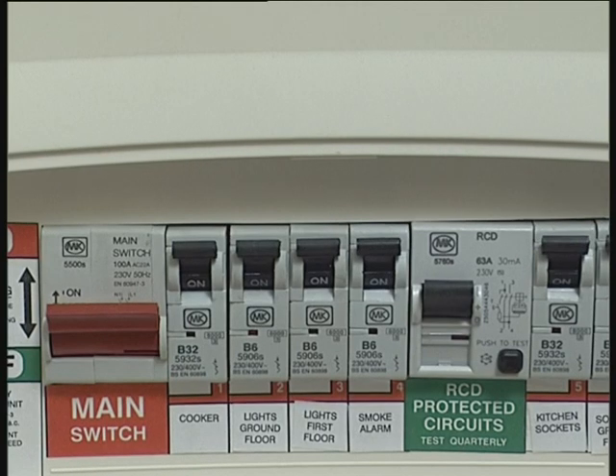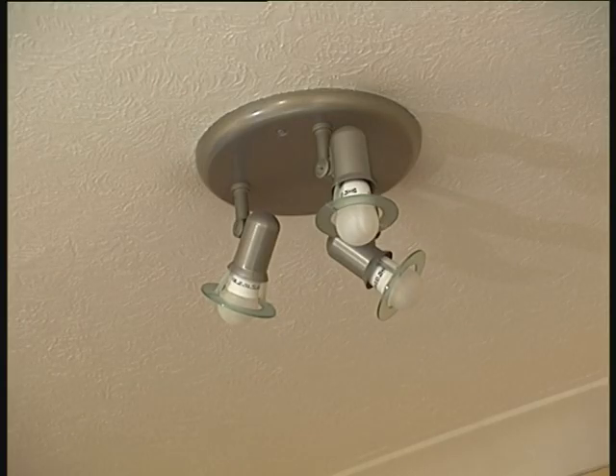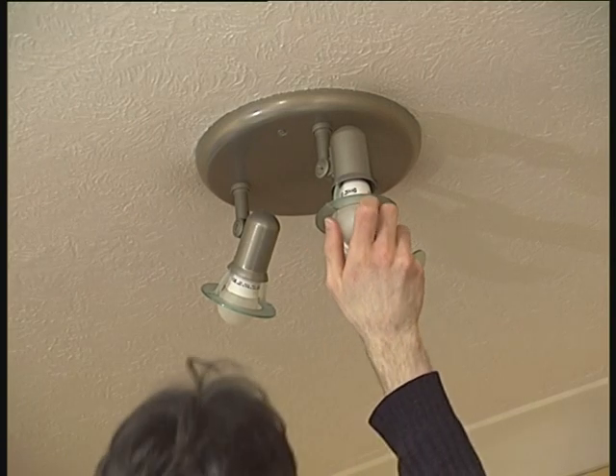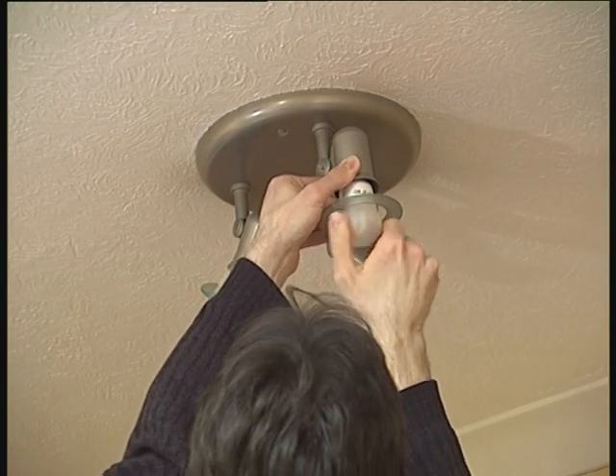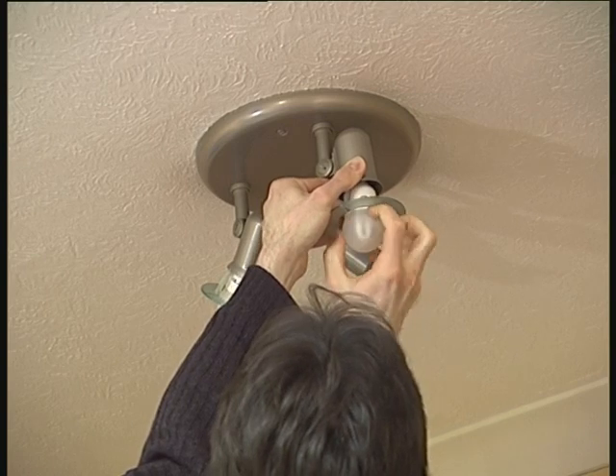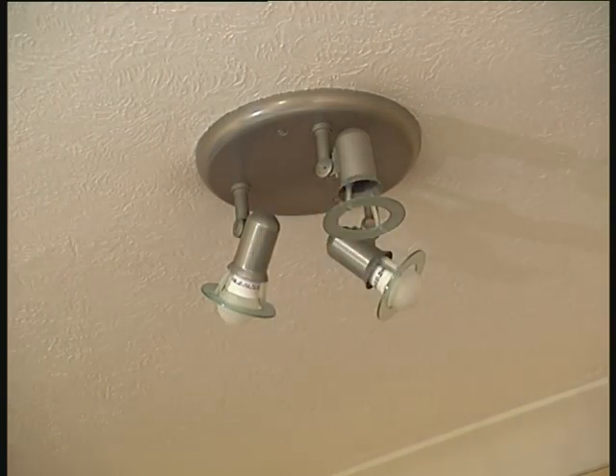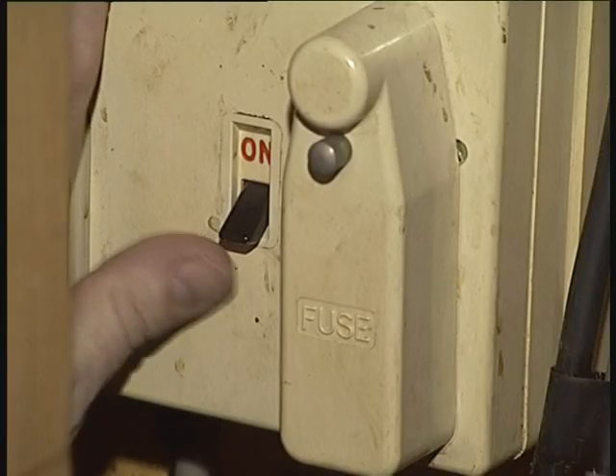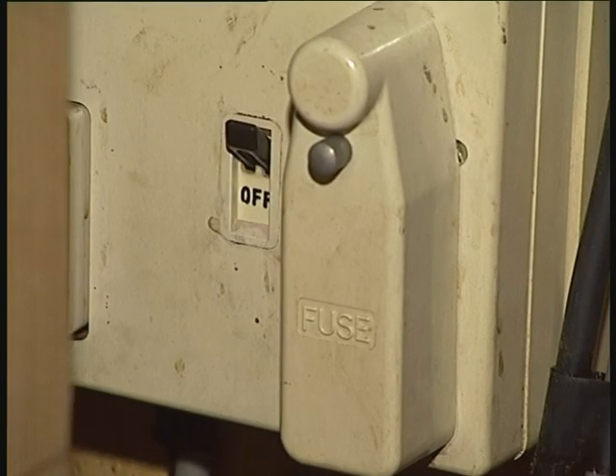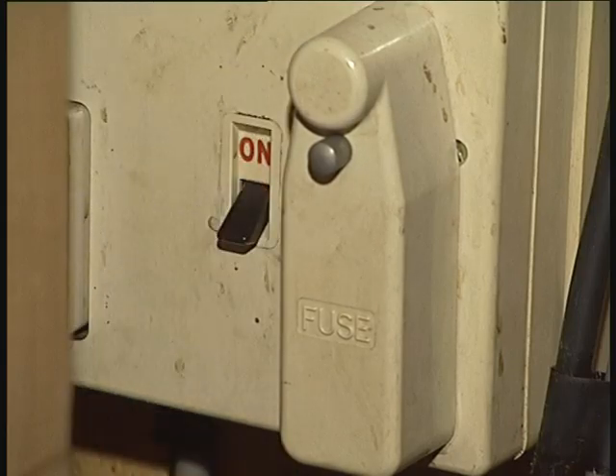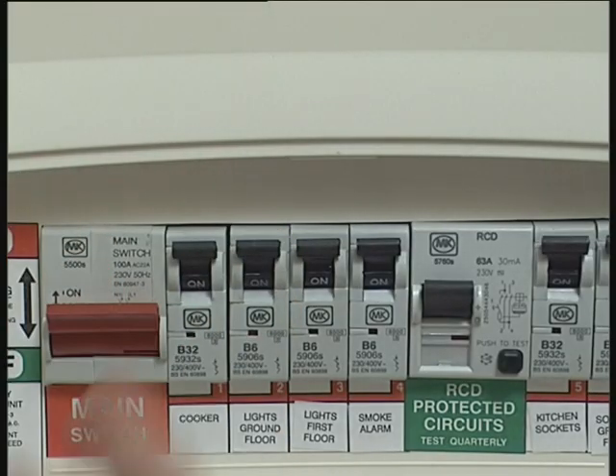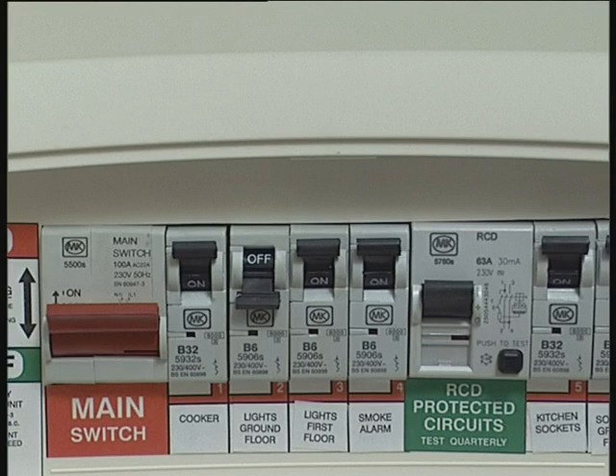Circuit breakers also operate far faster than a fuse. Before replacing a fuse or resetting a circuit breaker, it is vital to try and find the fault which caused them to operate. It may be just as simple as a lamp blowing. When replacing a fuse, the main switch should always be switched off. If the fuse blows again when the main switch is switched on, or the circuit breaker trips again when you reset it, there is something seriously wrong with the circuit, and you should send for an electrician.